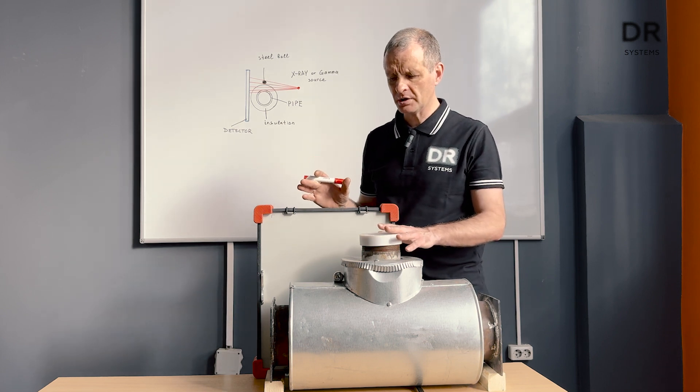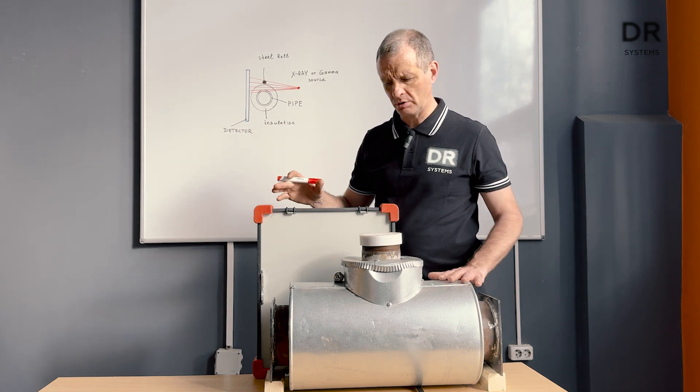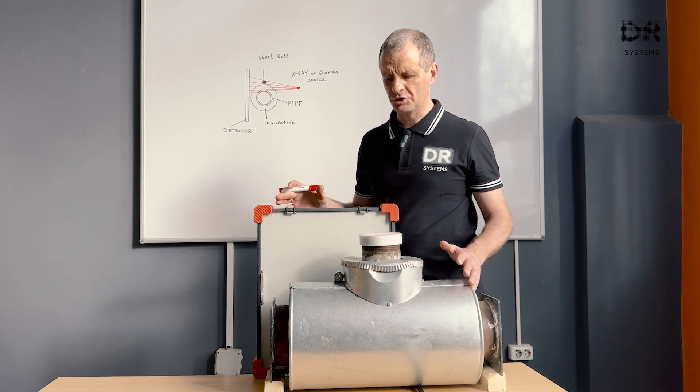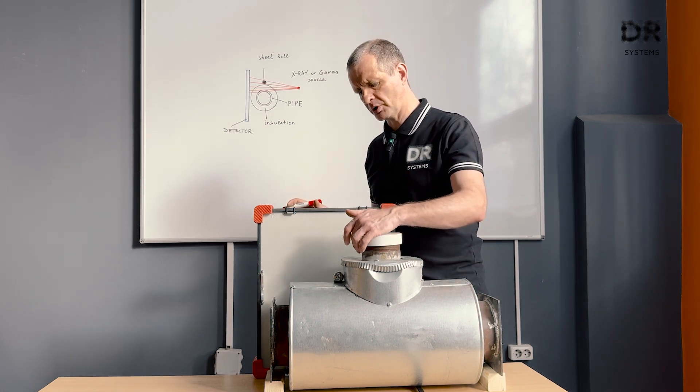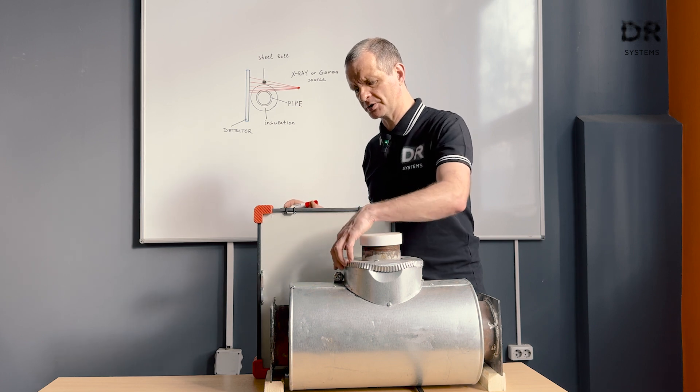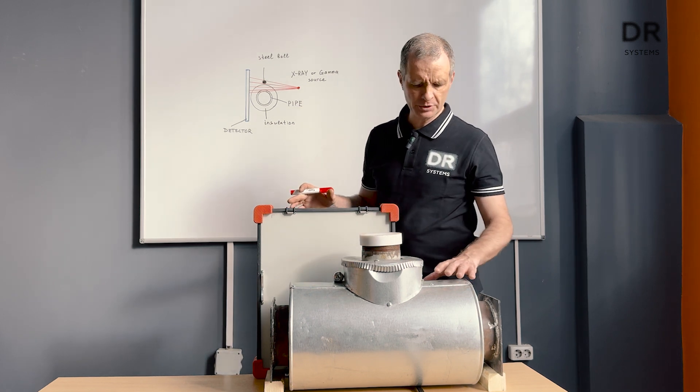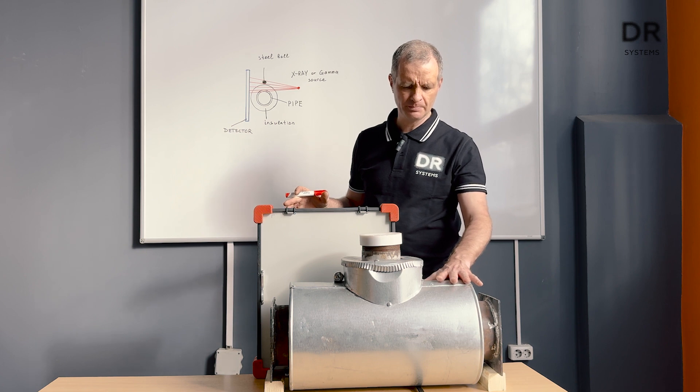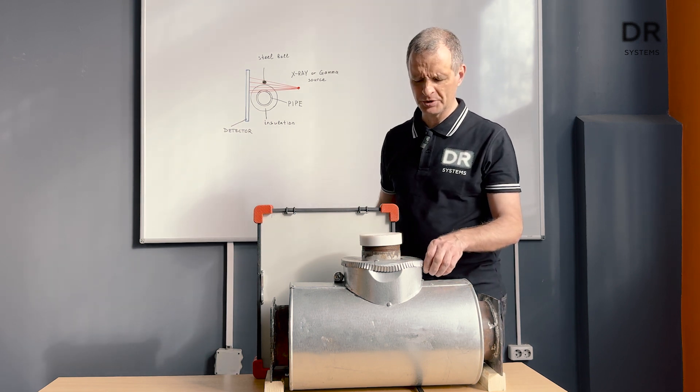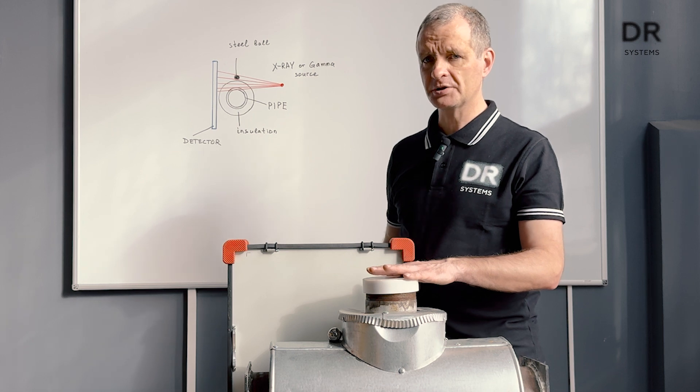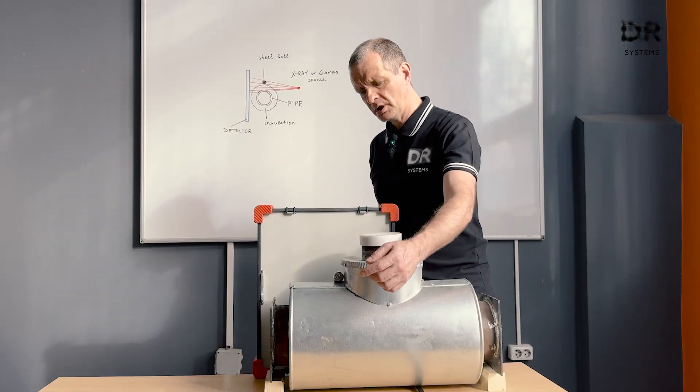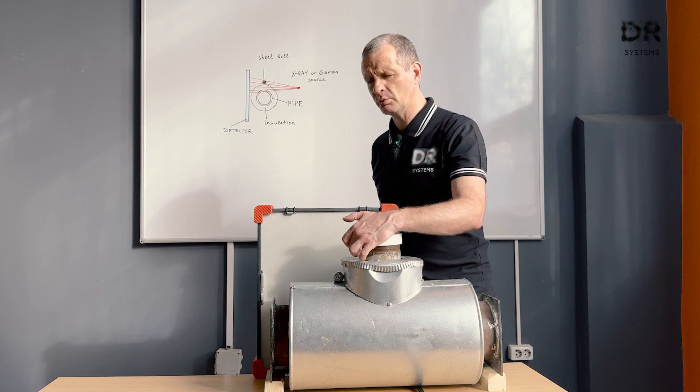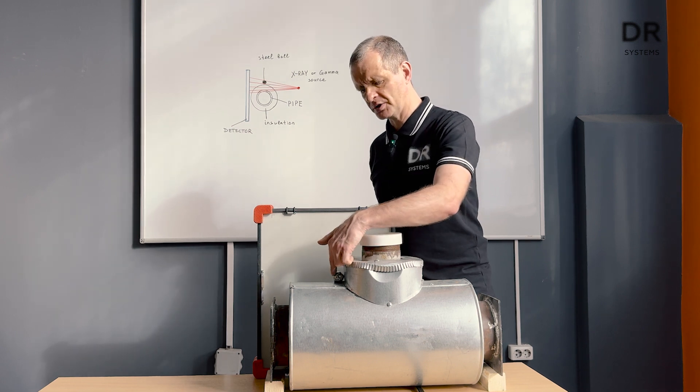It's not a good idea to try to measure all the walls at one image. If we are interested to measure this part of the pipe, the steel ball must be here. If we want to measure this pipe, we move the detector and we move the ball here.